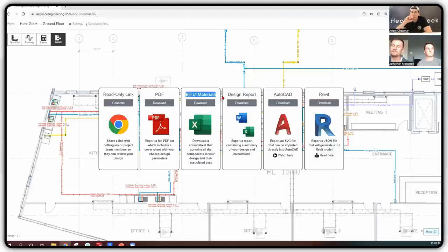All right, quick question on the radiator. So let's say we select a 3 kilowatt radiator. How does it know? Do you put in a delta T for the radiator, i.e. what it's 3 kilowatts at? Because there's a standard for radiators, I don't know what your understanding is, but the standard is a delta T50, so it sits at 50 degrees above the air temperature to give you 3 kilowatts. Obviously, for heat pumps, we want that more like 20. So is there a way to adjust that in here and it would adjust the radiator size, or would we have to do that link ourselves in the app?